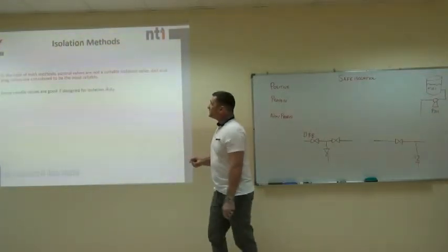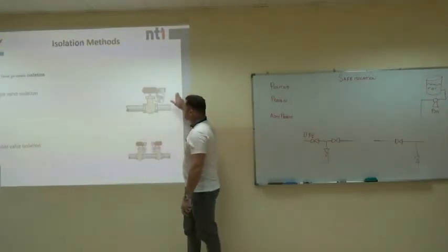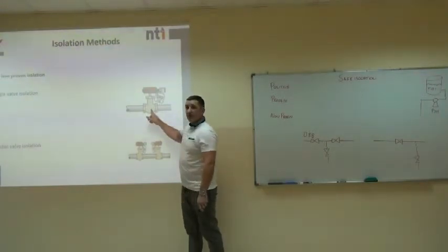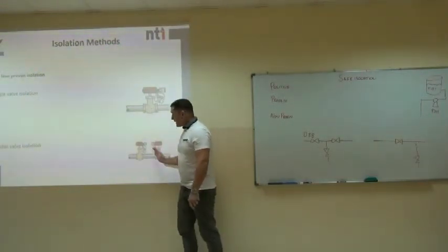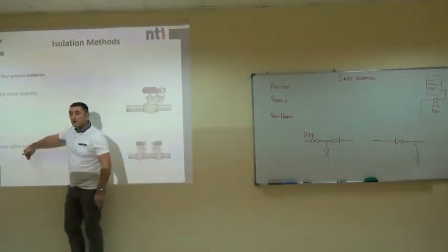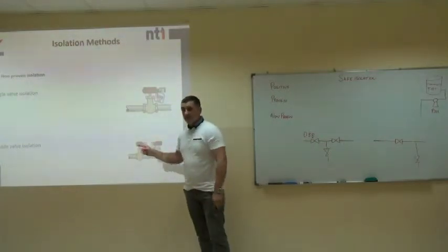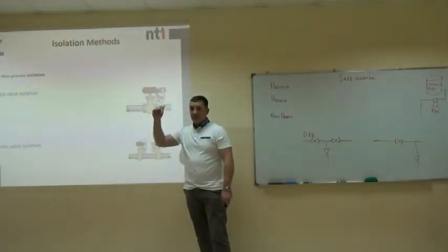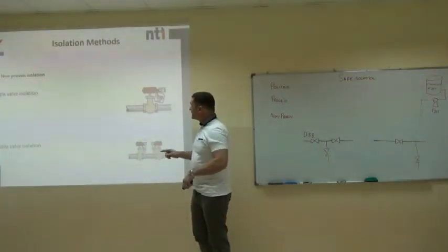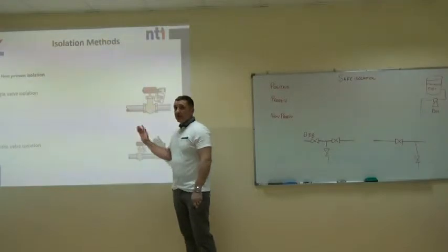The lowest form of isolation is non-proven isolation — that would be just one valve closed. There is no way of proving whether that valve is passing or not. It might be two valves closed, or even ten valves all in a line, all closed — that is still the lowest form of isolation and is very dangerous. So: positive isolation is separation of the line and fitting a flange; proven isolation is double block and bleed or single block and bleed; non-proven is single valve or multi-valve.